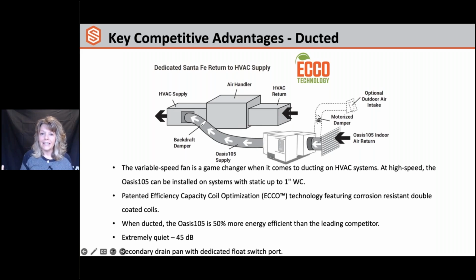So originally our dehumidifiers weren't designed to be in living spaces. They were designed to be in a mechanical room away from the rest of the house, in the attic, in the basement, in the crawl space. But now that we're seeing mechanical systems more and more integrated into a closet in the living space, noise is becoming more of an issue. So that 45 decibels is important. And again, you got that secondary drain pan with a dedicated float switch port right on the unit.